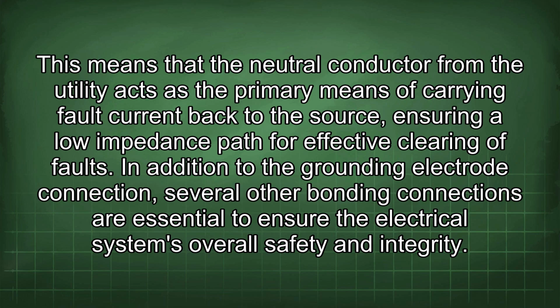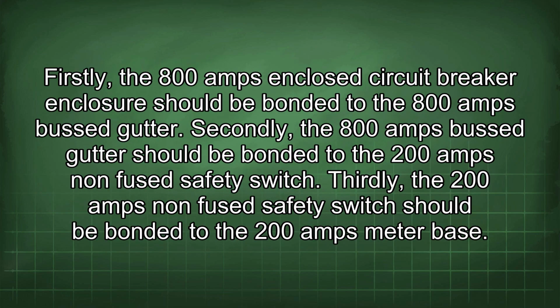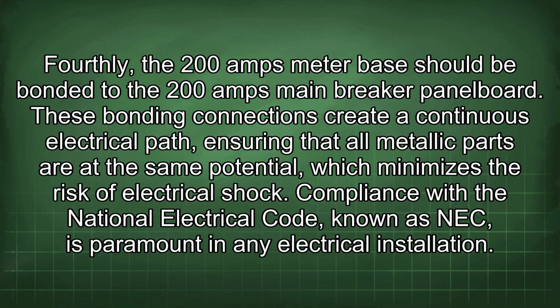In addition to the grounding electrode connection, several other bonding connections are essential to ensure the electrical system's overall safety and integrity. Firstly, the 800 amps enclosed circuit breaker enclosure should be bonded to the 800 amps bus gutter. Secondly, the 800 amps bus gutter should be bonded to the 200 amps non-fused safety switch. Thirdly, the 200 amps non-fused safety switch should be bonded to the 200 amps meter base. Fourthly, the 200 amps meter base should be bonded to the 200 amps main breaker panel board. These bonding connections create a continuous electrical path, ensuring that all metallic parts are at the same potential, which minimizes the risk of electrical shock.